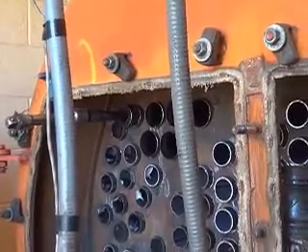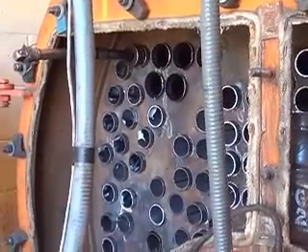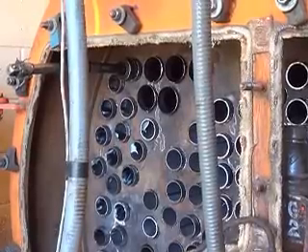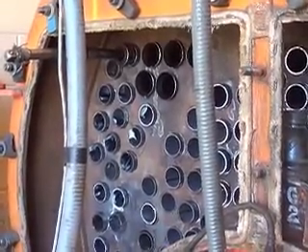Now you've got some sort of a lubricant on there? This is Crisco — Crisco shortening. That way it doesn't contaminate the water or the tube sheet. What are those tubes made out of — is that like a carbon steel, a soft steel? I think it's some kind of carbon — high carbon or something like that. And it looks like it's got a seam in the tube, so it's not really — you know — but it's probably a real round tube, a mandrel. They pull a mandrel through it to get it real smooth. But it conforms to just about anything — the tube sheet doesn't have to be perfect for this thing to seal.